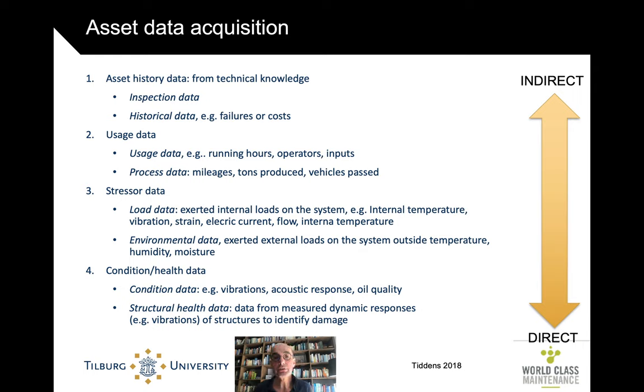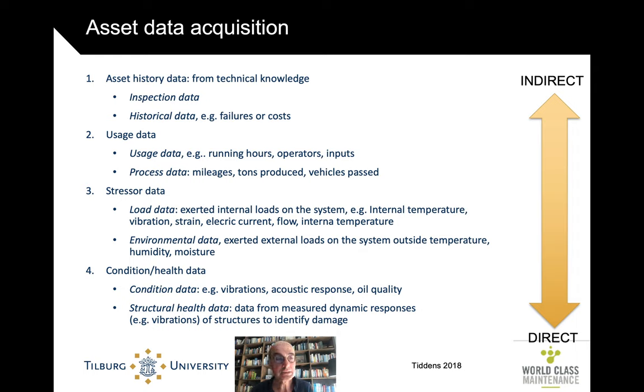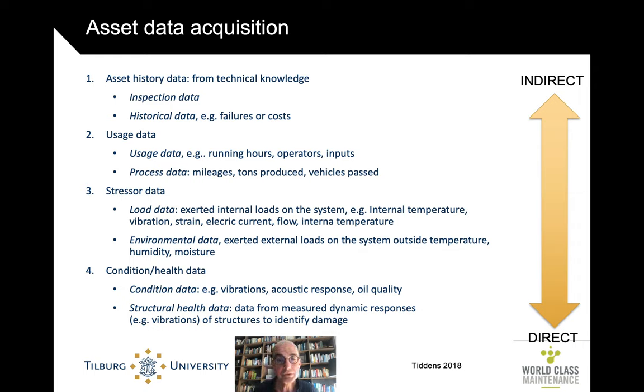Even more specific is not looking at the load on the system but at the actual condition of the asset. There you can look at vibration, acoustic response, and oil quality. Structural health data is collected specifically to see if there are damages — for instance, a composite part of an aircraft can be hit by something and show no external deformation, but inside there may be delamination. You can detect this by tapping with a small hammer to hear if the sound differs from a healthy part of the composite material.